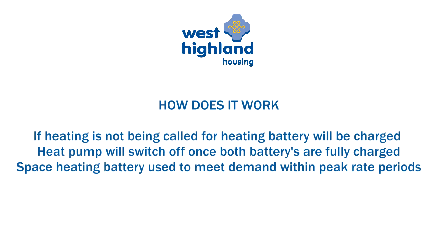At the lower rate times, once the hot water heat battery demand is addressed but there is space heating demand, the heat pump will initially divert heat direct to the radiators, assuming the space heating is being called for by your central heating programmer. As the rooms come up to temperature, the flow will be diverted to the space heating battery and continue until the space heating battery is fully charged. If there is no space heating demand to the radiators, the heat will be diverted to the space heating battery, and the heat pump will switch off when heat and hot water demand have been met.